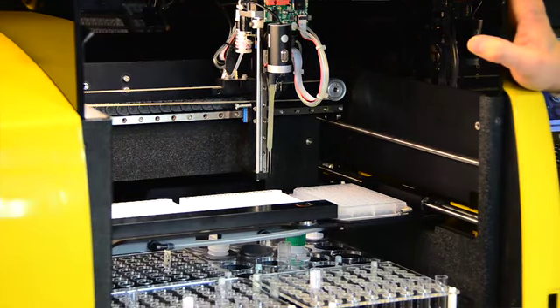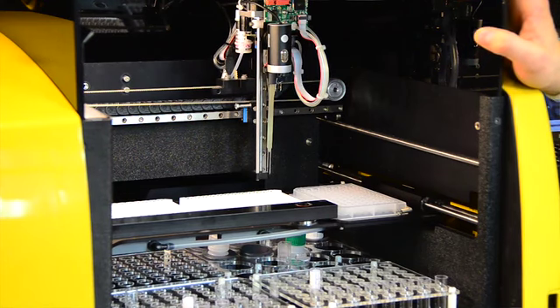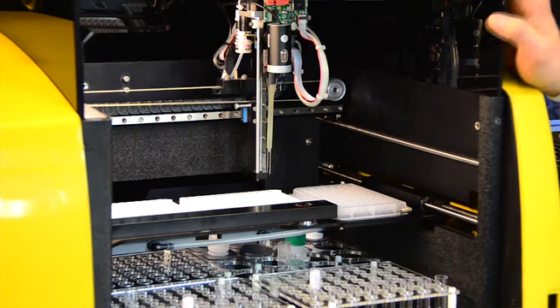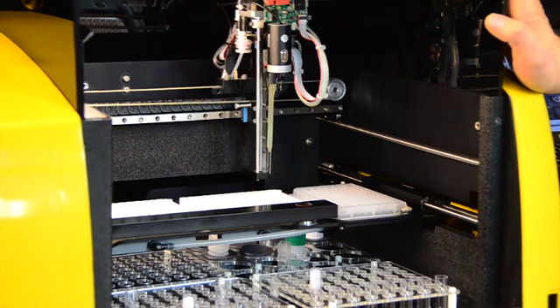Now, the other unique thing about the probe is that it is very difficult to break. The probe is not actually driven by the motor. The probe simply rests on a nut which is driven by the motor. So if the instrument is moving and the probe descends, you can actually stick your hand in there and not damage your hand. This also prevents you from damaging any caps or damaging the probe on any caps that are forgotten.